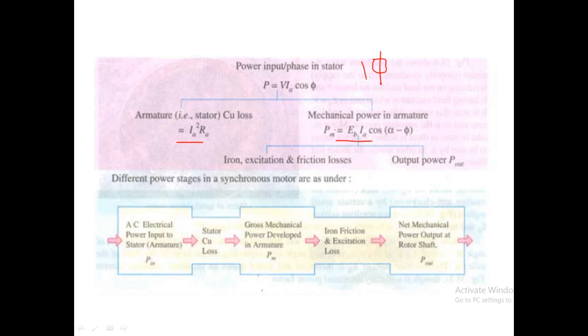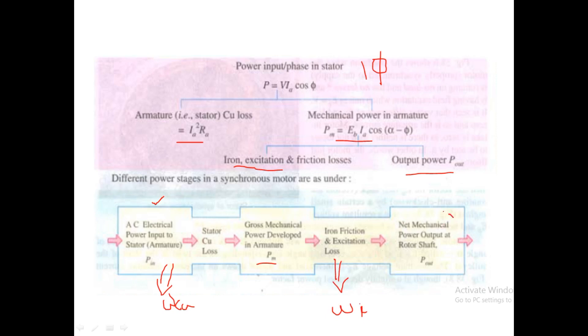In the mechanical power, a part of that power will be used for the output power or for conversion to torque, and one part will be used for iron, excitation, and frictional losses. There are different power stages in a synchronous motor. We give electrical power input to the stator; one part is lost as stator copper loss, and the remaining is the gross mechanical power development. From that, one part is lost as iron loss Wi, and the remaining is the net mechanical power development, P_net.